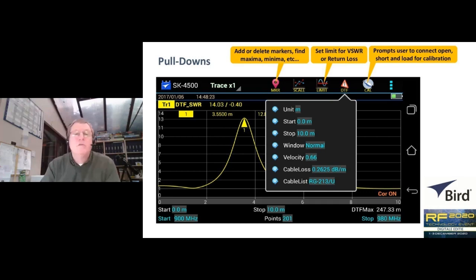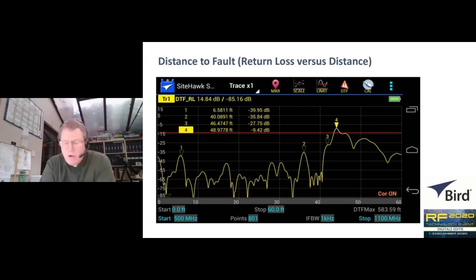Okay, that's VSWR versus distance. But VSWR is a fairly binary thing. It will tell us if something is good or bad, but it doesn't give us the detail we might want to see, and which would be displayed if we had return loss versus distance. And that's what we see in this next example. Just as an aside, I don't know if you can see it there, the previous example showed the distance in meters. If you now look along the x-axis, this time it's in feet. So as I said, the pull-down allows us to select either metric or imperial units for our American friends, and they're in feet in this example.